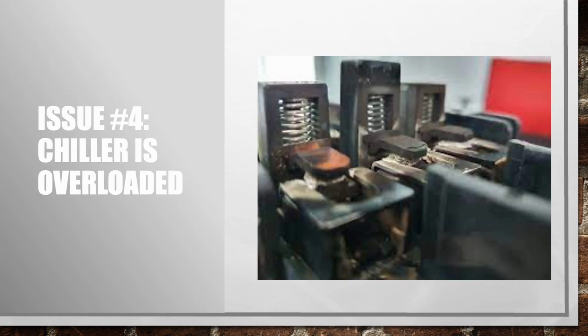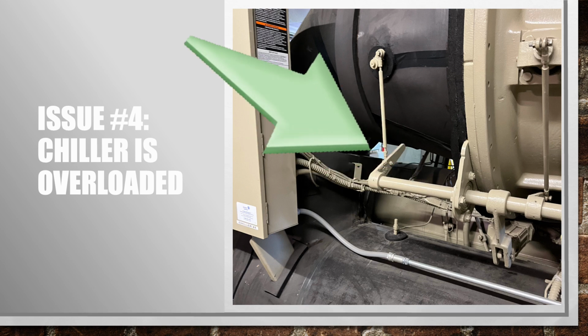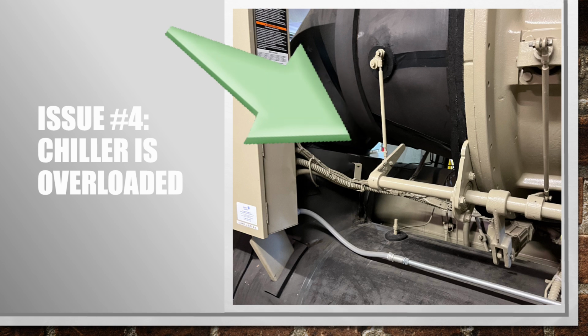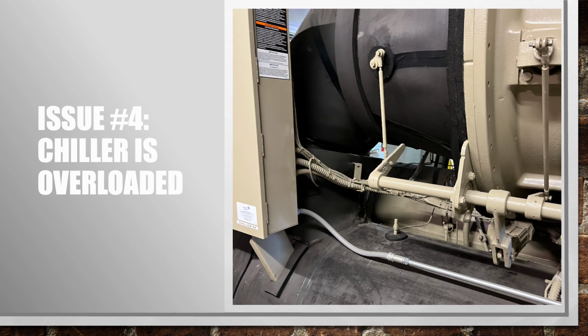Issue number 4, the chiller could be overloaded. I've had issues with this in the past where the inlet guide vane assembly is not working properly. Maybe the linkage is jacked up or something's bound up inside there, or the little pin is sheared or something stupid. That'd be the first thing I would probably look into because it's pretty easy to test.